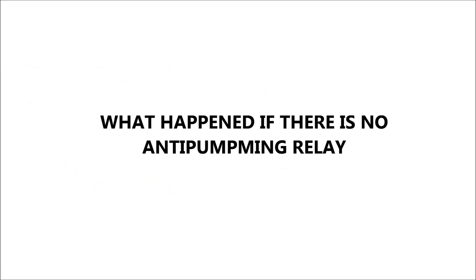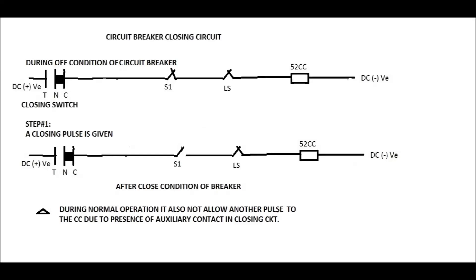Now, what happens if there is no anti-pumping relay? If no anti-pumping relay is used, the circuit diagram is as shown in this figure. In this case, if a closing pulse is given and we hold the control switch in the closed position — providing a continuous DC pulse to the closing circuit — the closing coil will energize and operate the breaker to make it ON, and the auxiliary contacts change their positions.